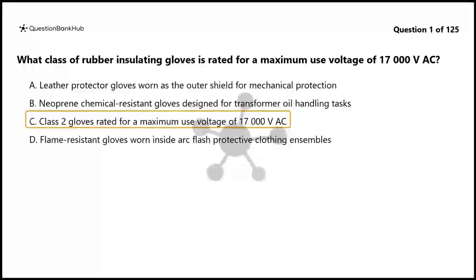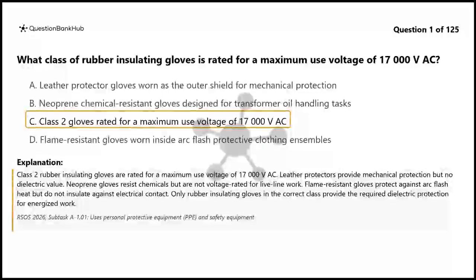The correct answer is C. Class 2 rubber insulating gloves are rated for a maximum use voltage of 17,000 VAC. Leather protectors provide mechanical protection but no dielectric value. Neoprene gloves resist chemicals but are not voltage rated for live line work. Flame-resistant gloves protect against arc flash heat but do not insulate against electrical contact. Only rubber insulating gloves in the correct class provide the required dielectric protection for energized work.